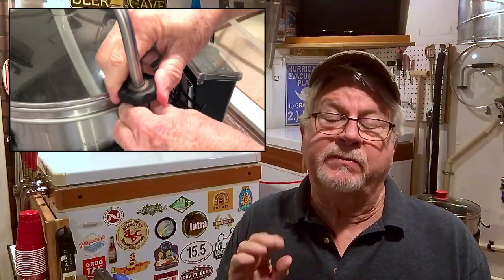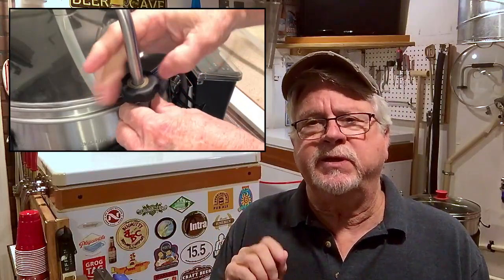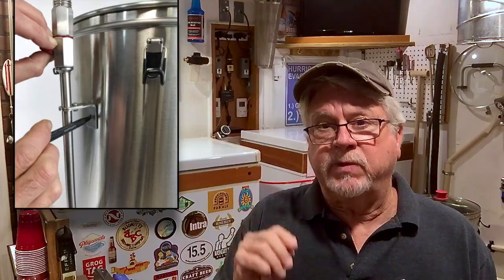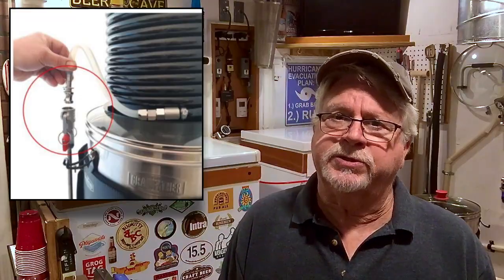Another recommendation is to always provide counter torque support to the discharge pipe safety valve when screwing and unscrewing the counterflow chiller's cooler connection knob or the recirculation arm's connection knob. Otherwise, the upper bracket will twist under the load and it could break the spot weld attaching it to the boiler. If it does break, there's a repair kit available on the web. If you want to avoid the torque issue altogether, there's a cam lock conversion kit that you can find on the web which eliminates the connection knobs and the torque issue.